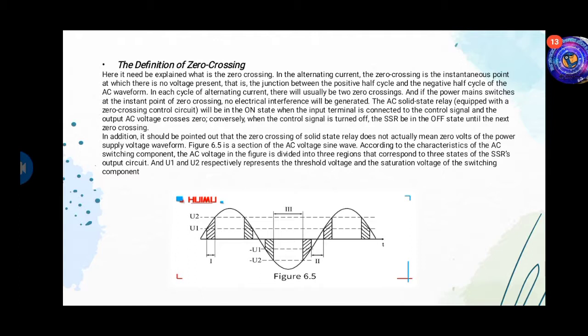The AC solid state relay equipped with a zero crossing control circuit will be in the on state when the input terminal is connected to the control signal and the output AC voltage crosses zero. Conversely, when the control signal is turned off, the SSR stays in the off state until the next zero crossing. In addition, it should be pointed out that the zero crossing of a solid state relay does not actually mean the zero volts of the power supply voltage waveform.